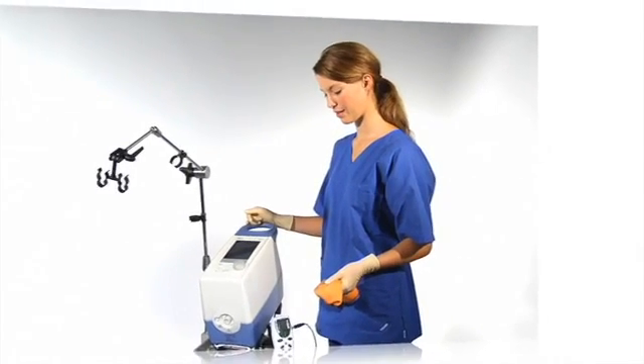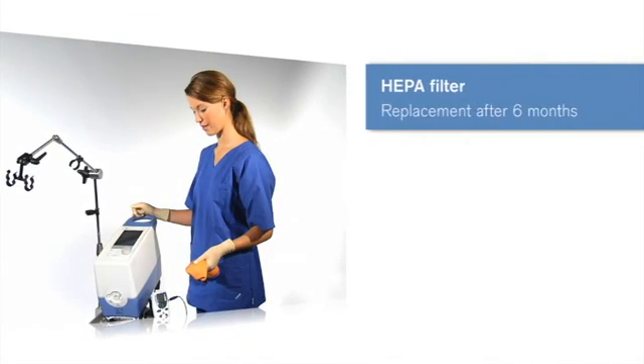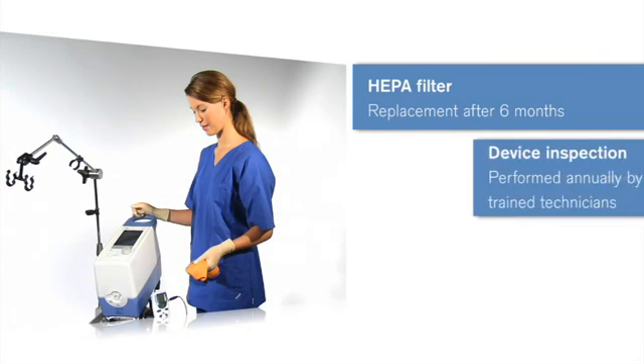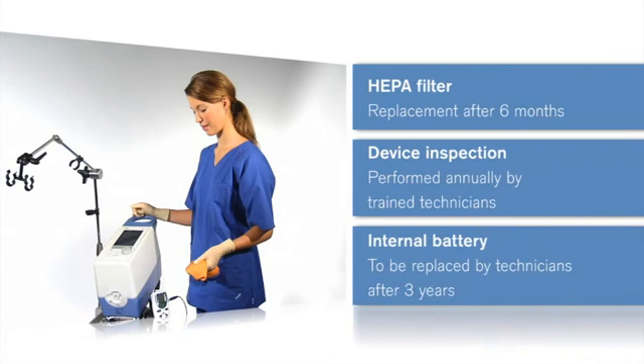Keep in mind the regular maintenance intervals: HEPA filter replacement after six months, device inspection performed annually by trained technicians, and battery to be replaced by technicians after three years.